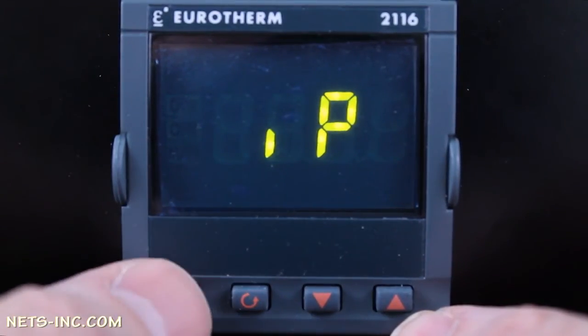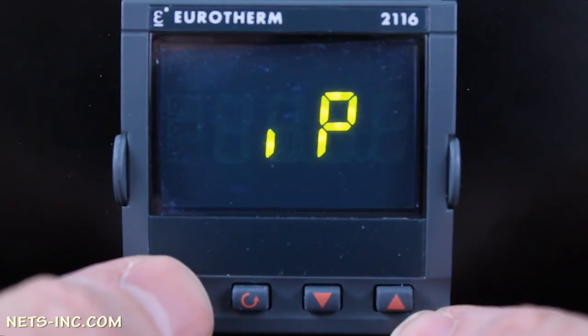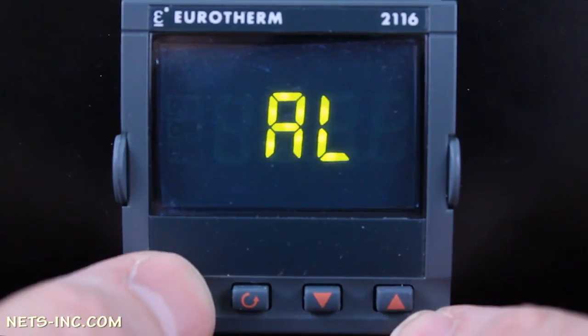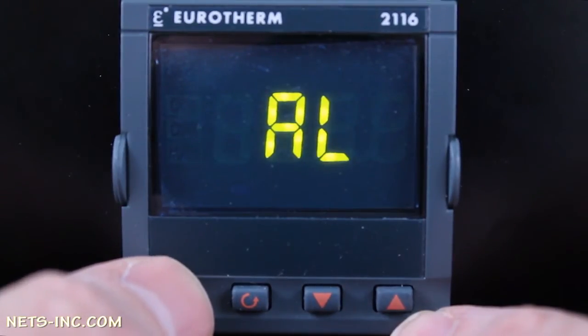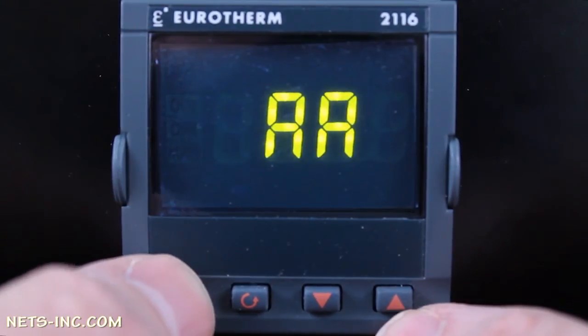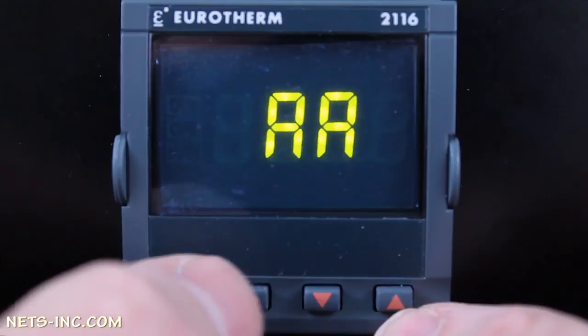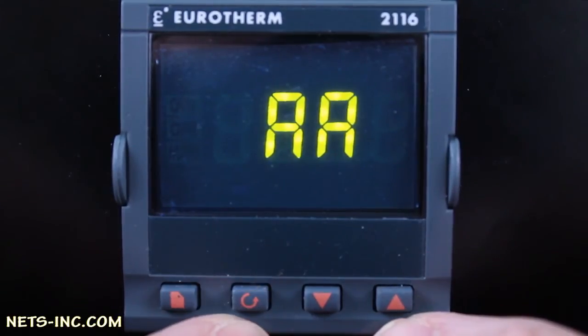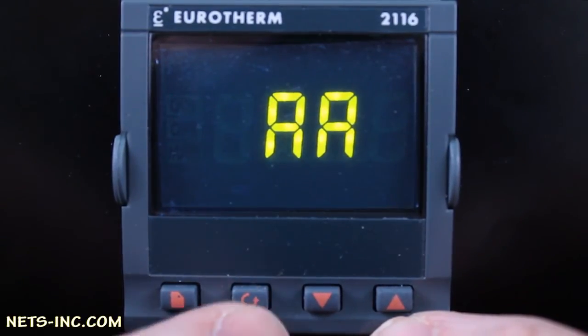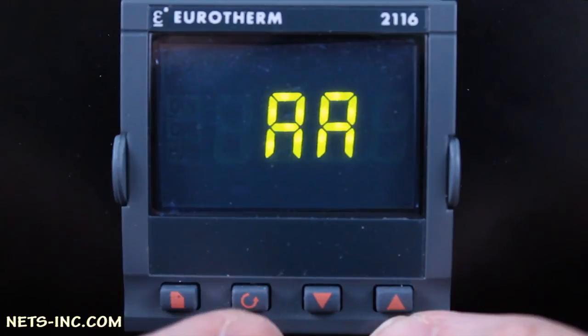Next, press the page key once to advance to the AL list. In this setup example, we are not configuring any alarms. Next, press the page key once to advance to the AA list. This is the AA relay output on terminals AA and AB. This output will be set up in this example as the cooling output.